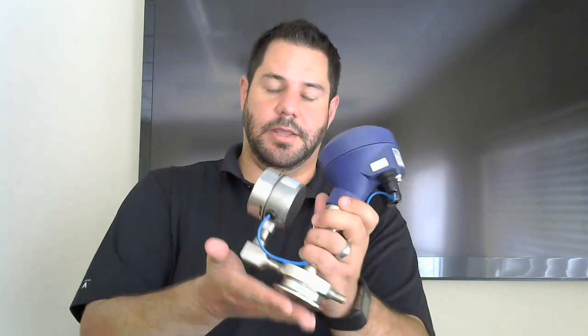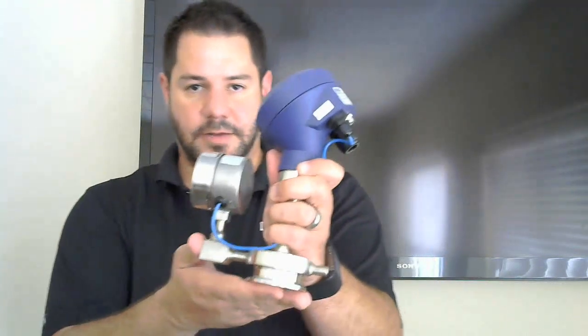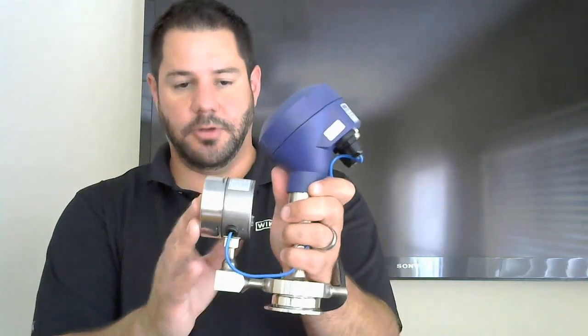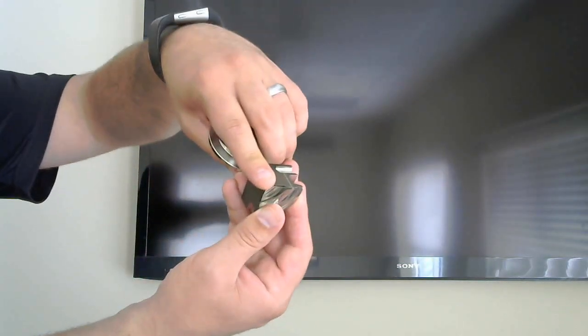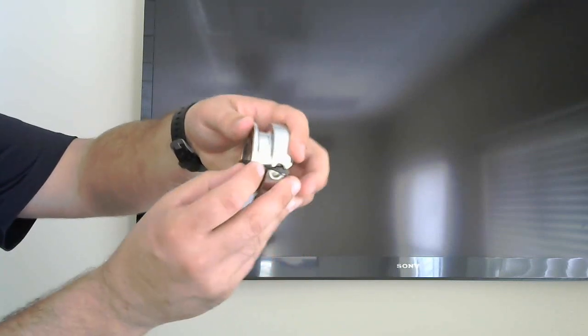A lot of pharmaceutical plants are using this typically on their final fill areas and things of that nature. Aseptic can be anywhere in the aseptic process, but it's one of the only gauges that can assure that. It's a patented device, and it can ensure and tell you if you have a diaphragm failure, so that you don't have product get contaminated with fill fluid or possibly the air. The other nice thing is, when you have that lower diaphragm fail, you've still got your secondary upper diaphragm, which is continuing to hold your fill fluid in it.